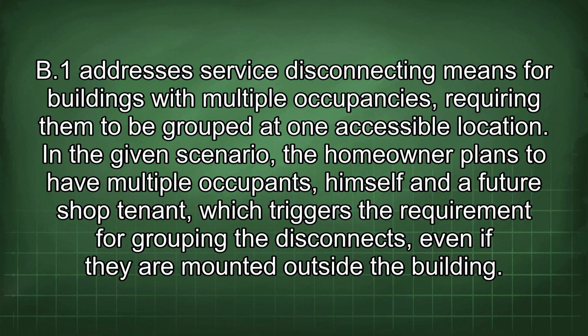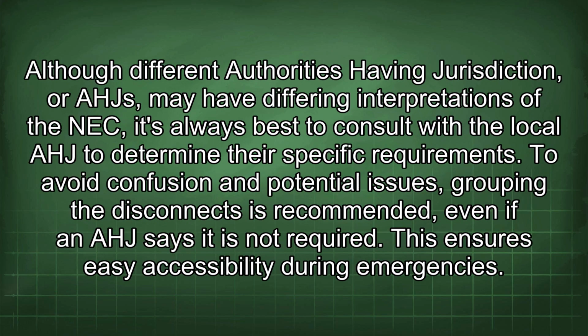In the given scenario, the homeowner plans to have multiple occupants, himself and a future shop tenant, which triggers the requirement for grouping the disconnects, even if they are mounted outside the building. Although different authorities having jurisdiction, or AHJs, may have differing interpretations of the NEC, it's always best to consult with the local AHJ to determine their specific requirements. To avoid confusion and potential issues, grouping the disconnects is recommended, even if an AHJ says it is not required. This ensures easy accessibility during emergencies.